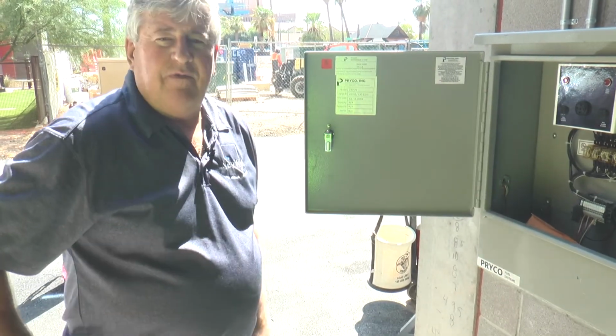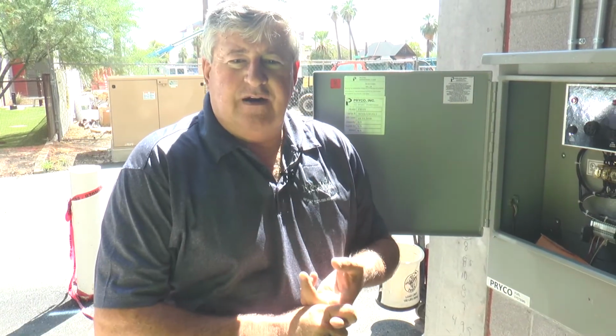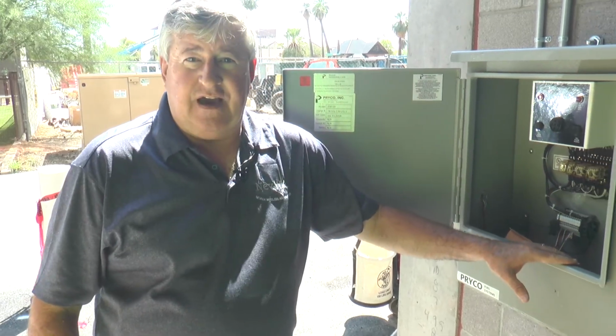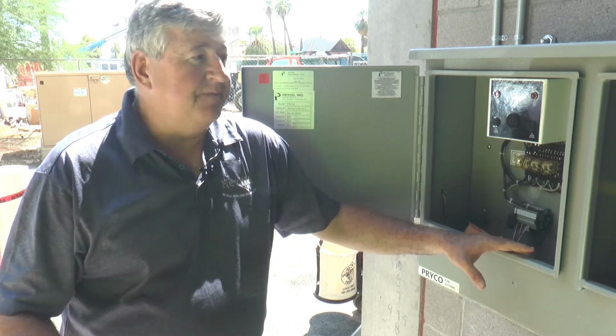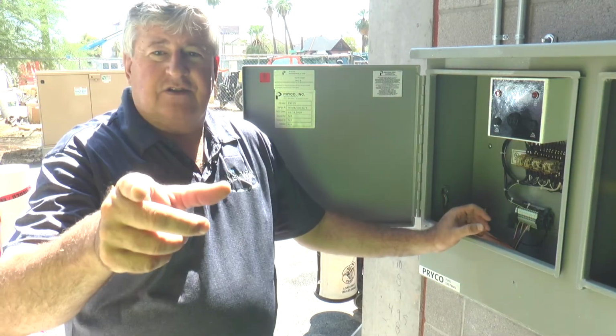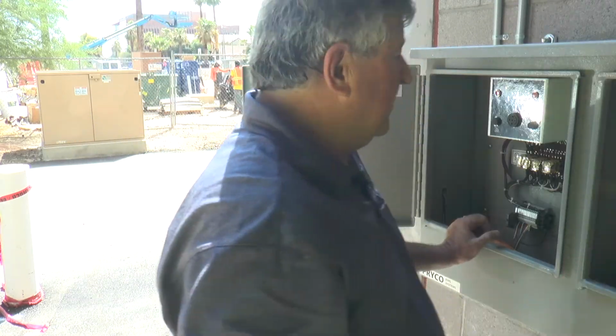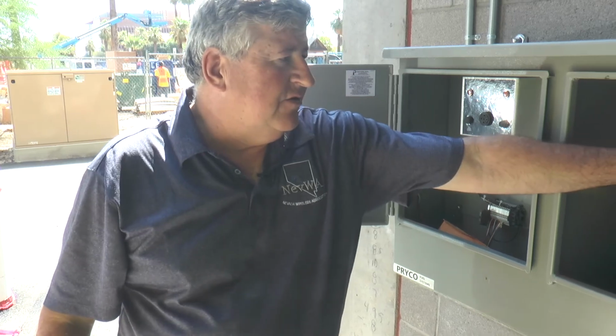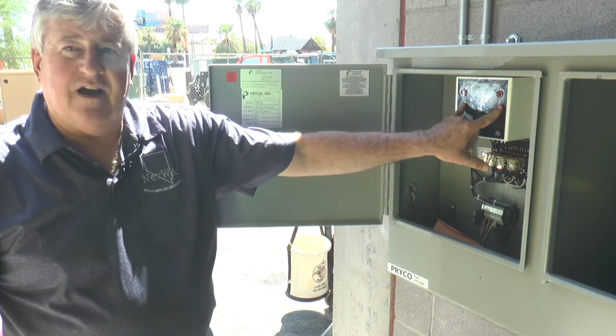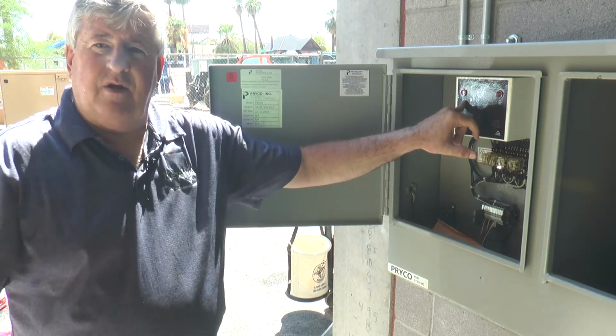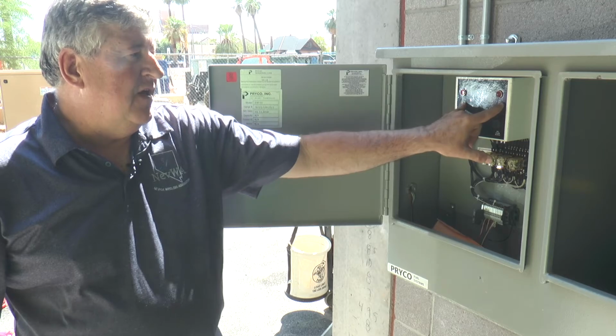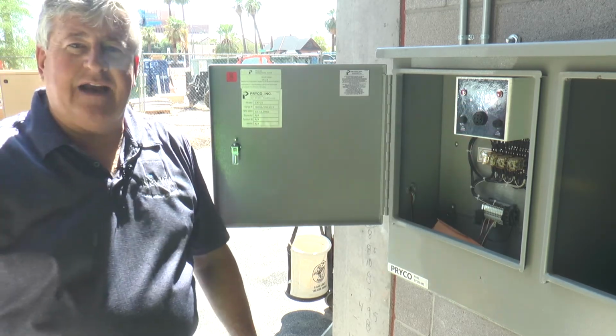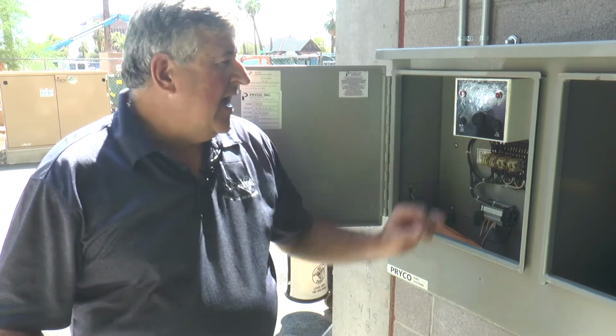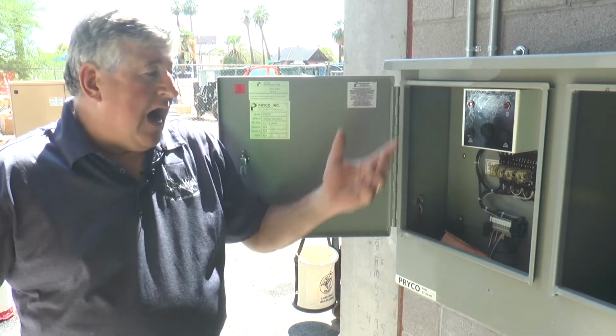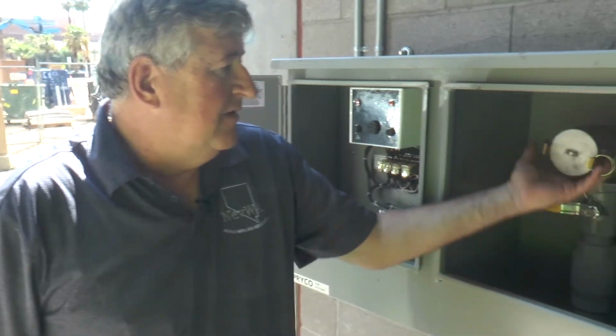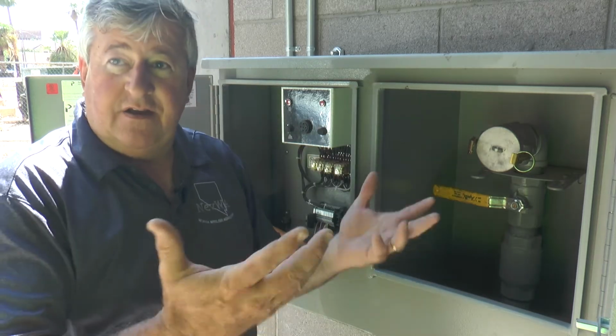Okay, now we're at the remote fill station for the generator set. When fuel is required for the tank, this is the means that City of Phoenix requires us to now fill the tank. No longer are you allowed to bring a fuel line into the building. The fill station is connected to a solenoid valve in the fuel line marked diesel fuel into the building. When an operator connects his fuel line to the port, there's a 90 and 95% alarm. At 90%, it'll alarm, let him know he needs to shut the fuel off. If he fails to shut the fuel off, there's a 95% alarm. That alarm also will activate the solenoid valve, preventing him from overfilling the tank. At that time, it'll also give a horn. Operator then closes his valve, disconnects, cleans up with fuel, closes it up, and he's all set, ready to go.